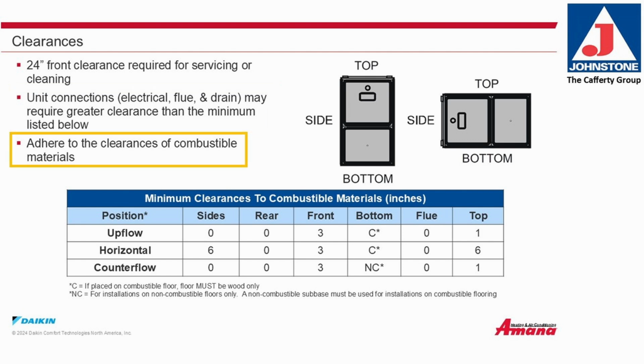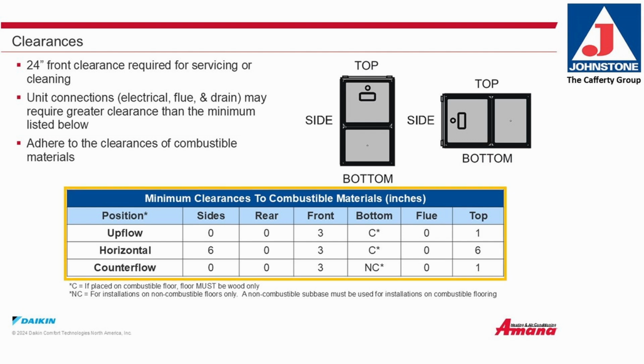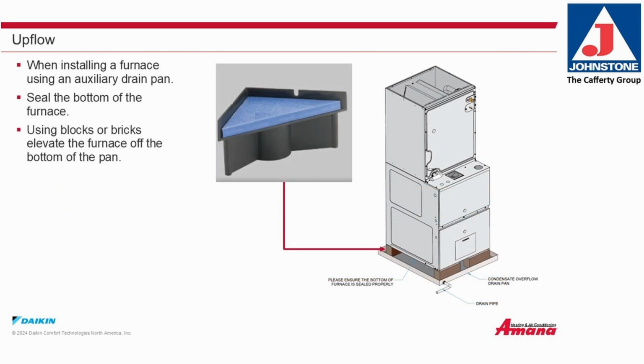Adhere to the clearances of combustible materials. For upflow or horizontal installations, if they are to be placed on a combustible floor, the floor must be wood only. For counterflow installations, installation is for non-combustible floors only. A non-combustible subbase must be used for installation on combustible flooring. Upflow. When installing a furnace using an auxiliary drain pan, seal the bottom of the furnace.